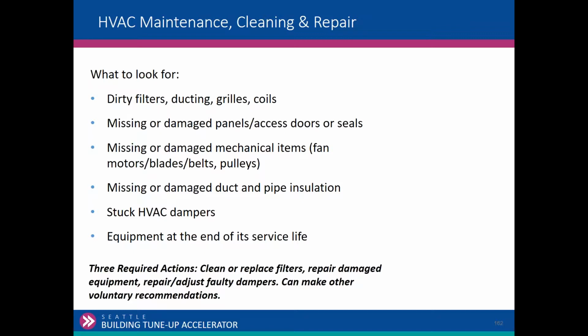This is your judgment: boy, you've got some general maintenance. Before you can tune up, we need to get the filters changed. We need to get some duct leaks fixed. I feel there's duct leakage, there's rotted flexible joints that need to be replaced. The coils are dirty. The outdoor condensing unit is full of leaves. It's just some general cleaning stuff. Missing or damaged access panels or door seals. Spacer bars missing from the filter rack. Those types of things. Missing or damaged mechanical items.